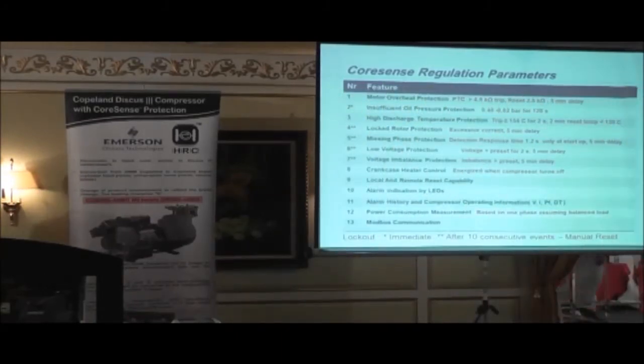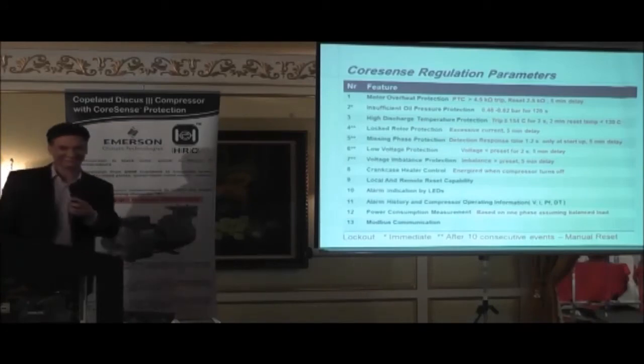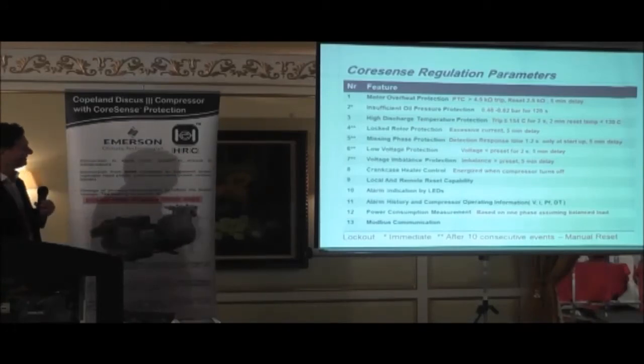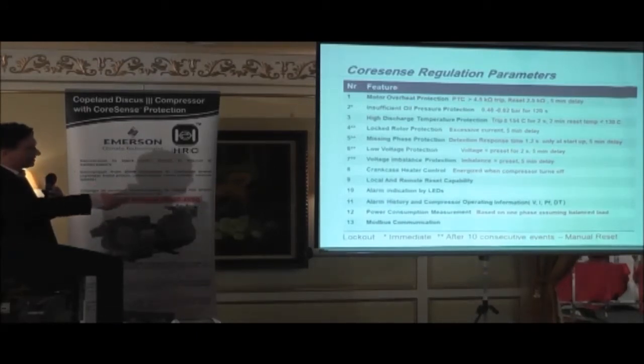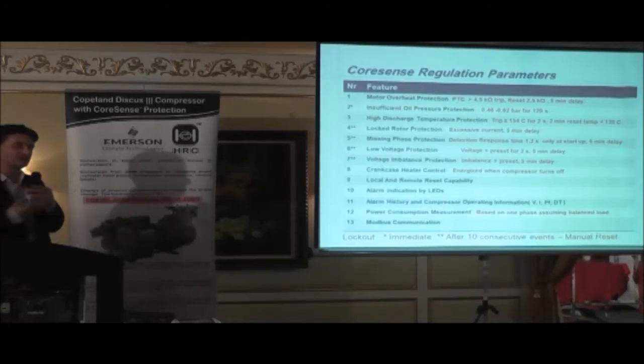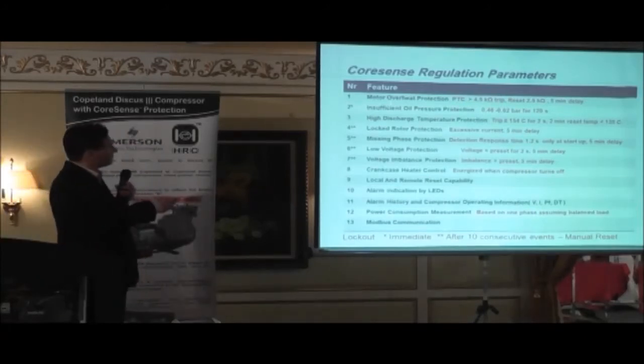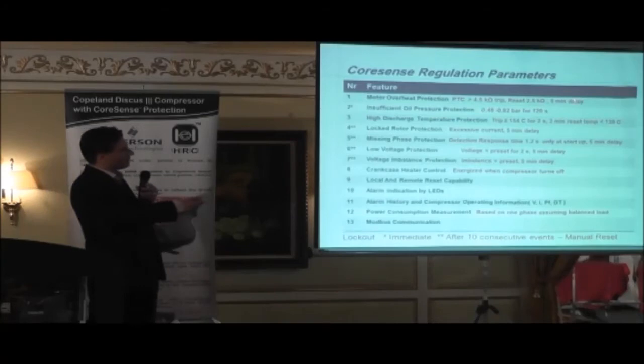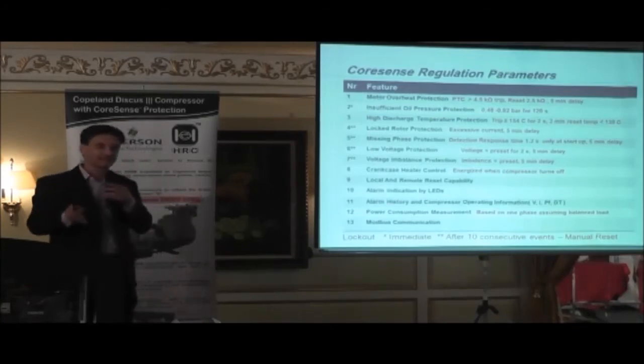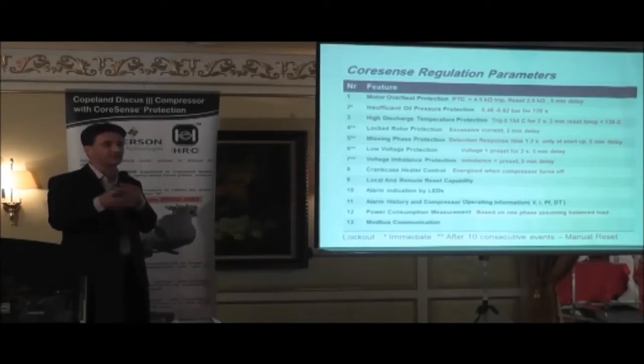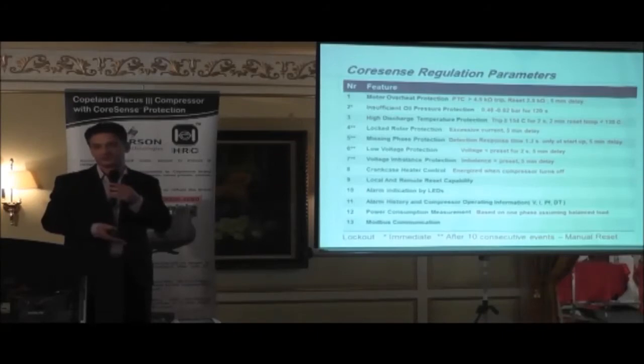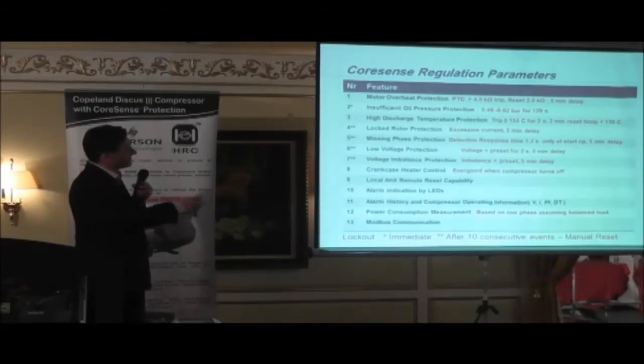I think that was the wake-up signal, yeah? Okay, so what I'm going to do very quickly and simply is go over what the regulation parameters are for each one of these safety features. If you look at item 1 and 2, the regulation parameters are exactly the same as what the INT69 was doing, and the OPS1 or the OPS2, or if you were using a mechanical oil pressure switch. So in terms of the parameters, nothing has changed.